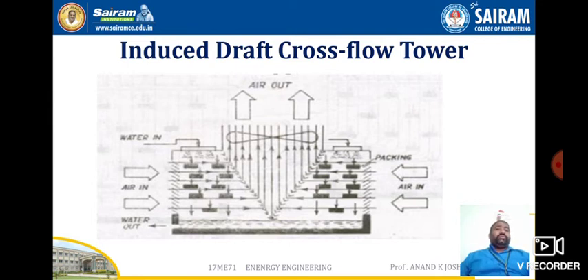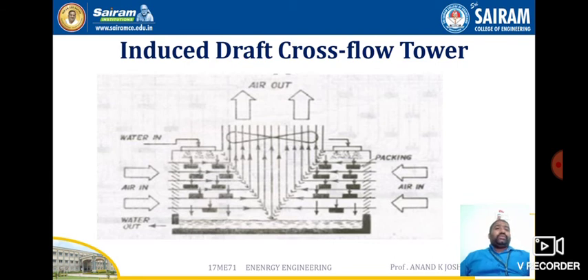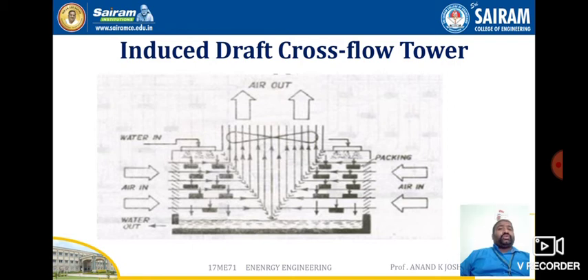The induced draft cross flow type tower provides horizontal airflow from both sides of the tower. Water falls in the form of small drops over a filling. The fan is centered at the top of the unit and draws air through cells paired to a suction chamber between the fan sections. The outstanding feature of this tower is lower air static pressure losses due to less resistance in the airflow.